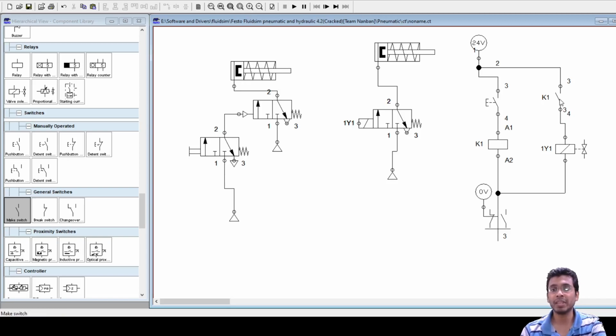Why? If you see a relay, what is a relay? A relay is an electromagnet, where you have your armature currents. These armature currents are generally low and they work with low voltage, so it may trigger using a 24 volt system or whatever it is, but all the contacts of this relay may work in an altogether different voltage or current system. For example, that may function with 220 volt, or any other 440 volt or whatever it is, that system.